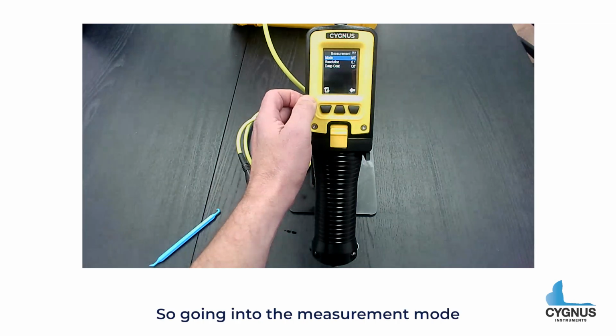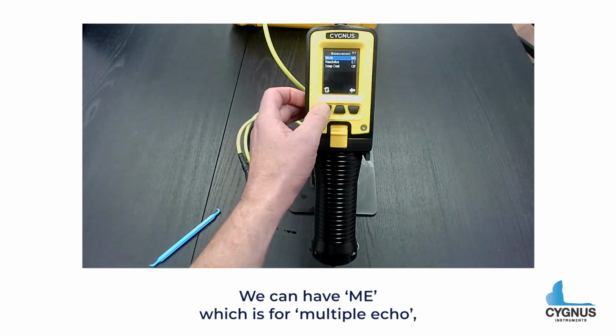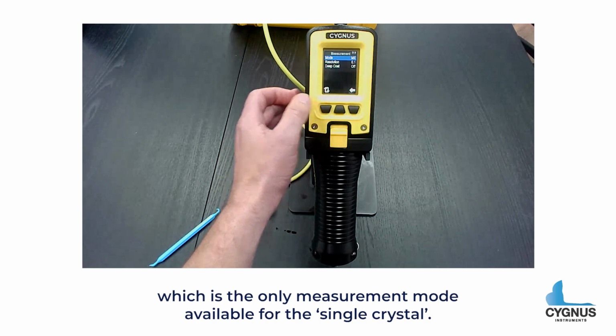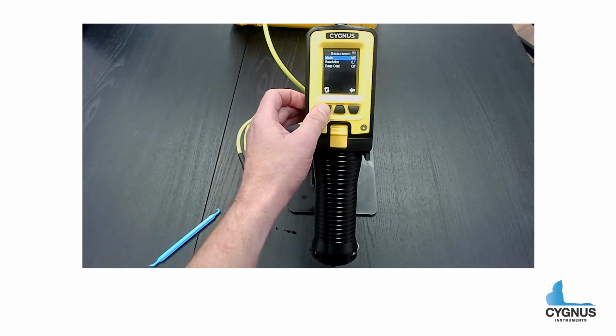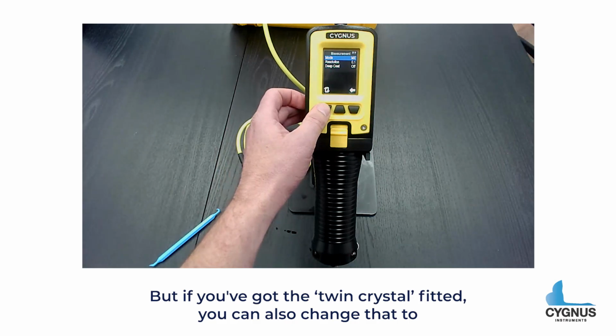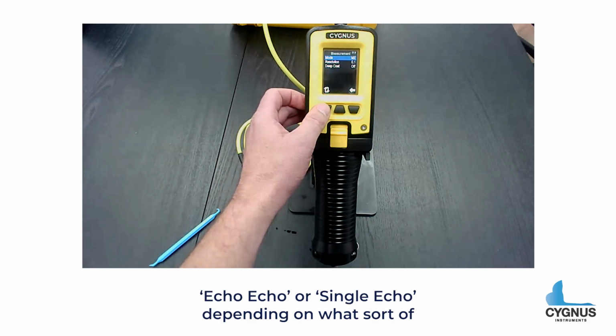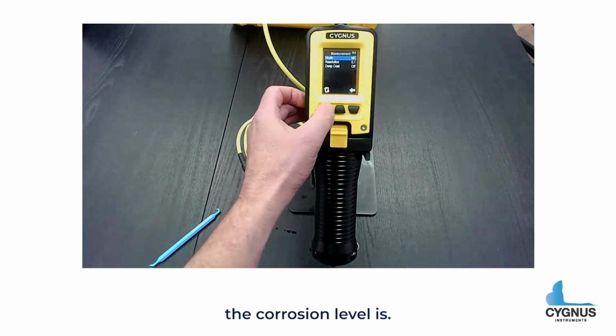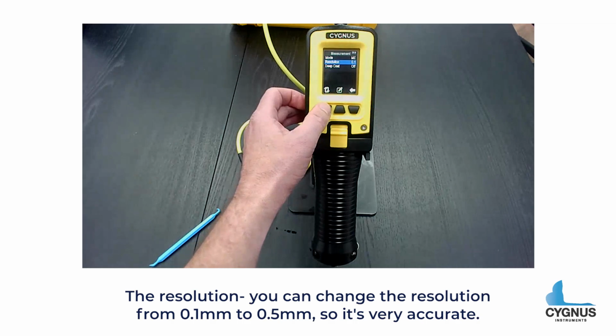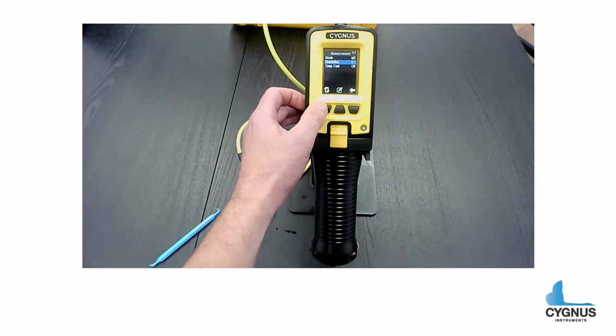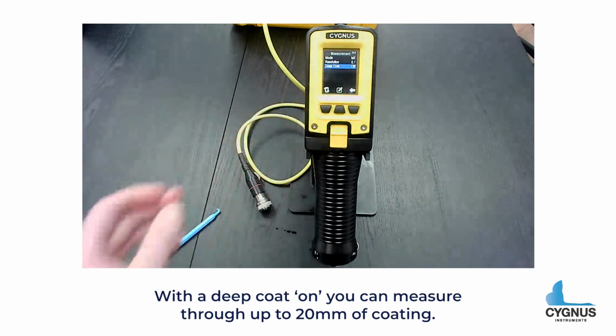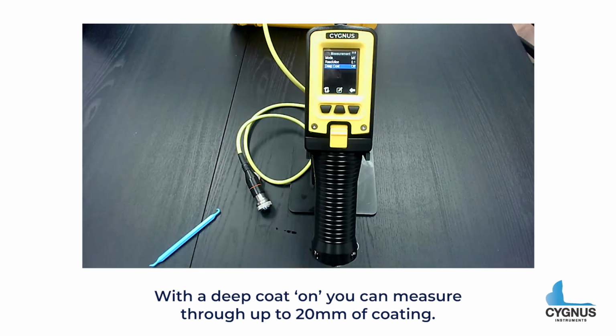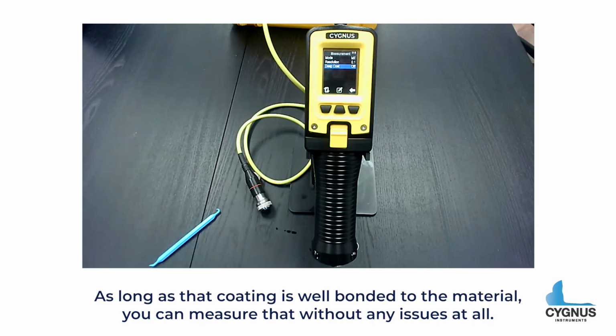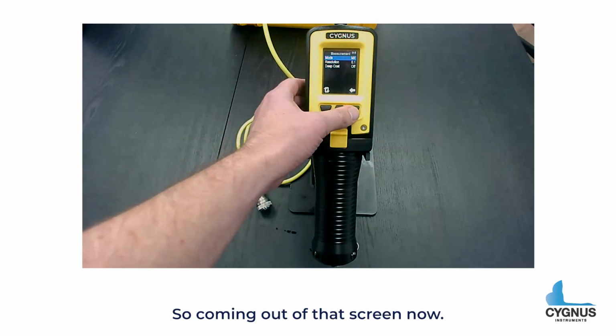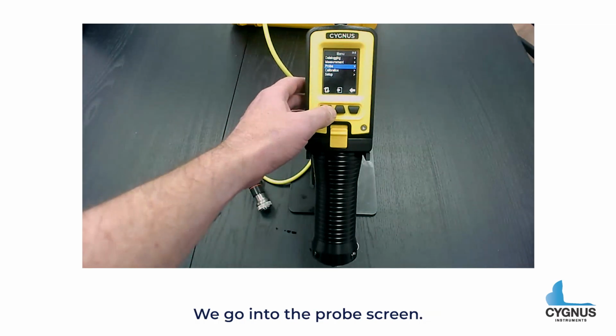Going into the measurement mode, over here we have the different measurement modes. We can have ME, which is for multiple echo, which is the only measurement mode available for the single crystal. But if you've got the twin crystal fitted, you can also change that to 'Echo Echo' or 'Single Echo', depending on what sort of corrosion level it is. For the resolution, you can change it from 0.1 of a millimeter to 0.05 of a millimeter, so it's very accurate. And then you've also got your deep coat on or off. With deep coat on, you can measure through up to 20 millimeters of coating, as long as that coating is well bonded to the material, you can measure that without any issues at all. So coming out of that screen now, we go into the probe screen.